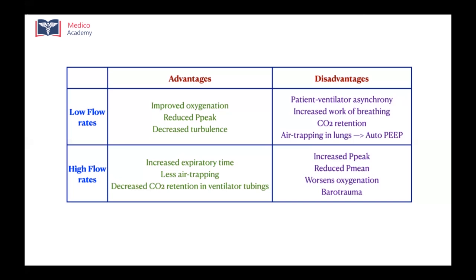So you need to understand that if the P peak or the P plateau rises, P peak is peak airway pressure, P plateau is the airway plateau pressure, if those rise, barotrauma will happen. And if the mean airway pressure, or the P mean, rises, it can result in better oxygenation. But when you keep high flow rates, the P mean reduces, resulting in reduced oxygenation. So this table tells you the advantages and disadvantages of low and high flow rates. As I said earlier, for most patients, 60 to 80 liters per minute of flow is adequate. But if you have a patient with chronic airflow obstruction pathology, then try to keep flow rates higher than 100 liters per minute. Okay, so that's about inspiratory flow.